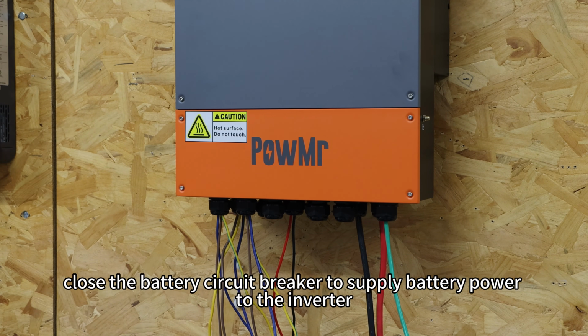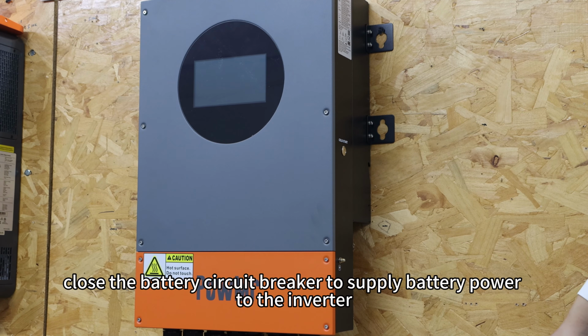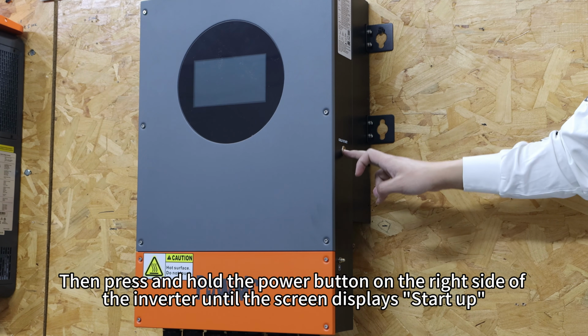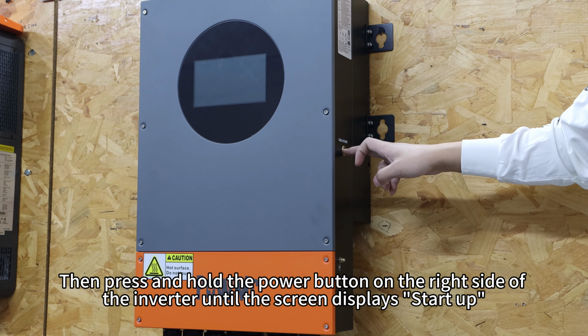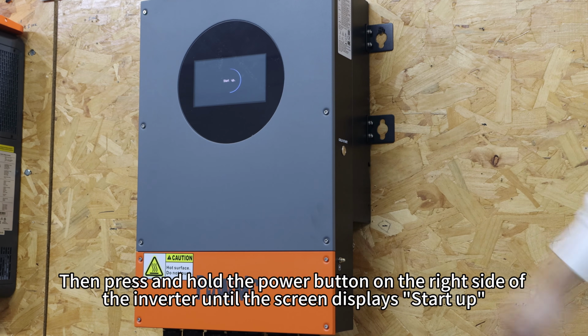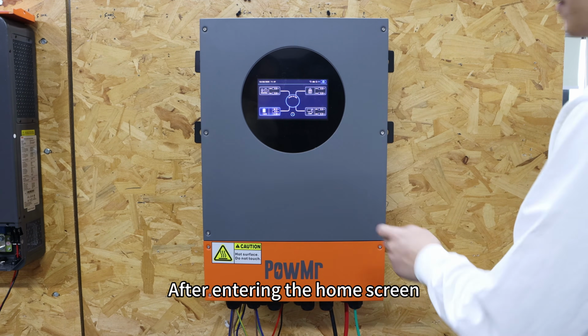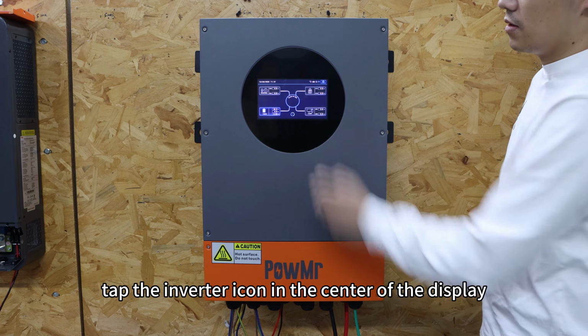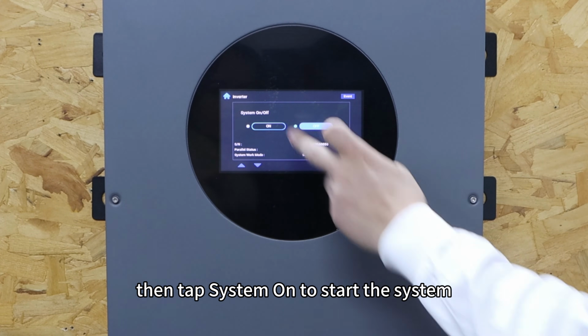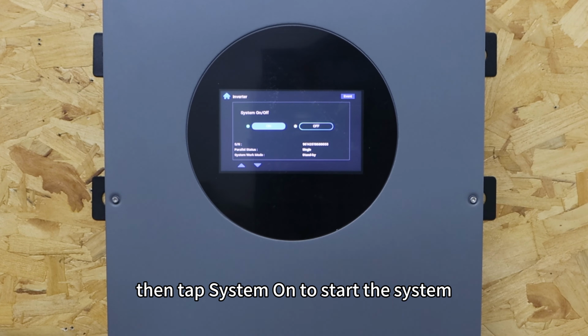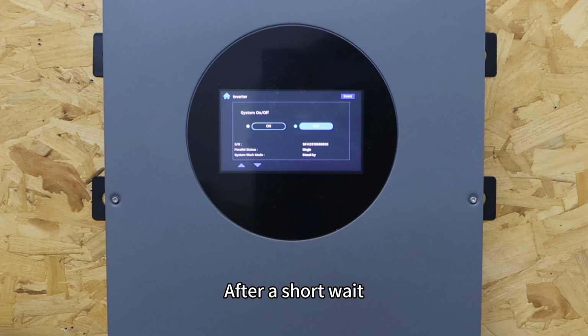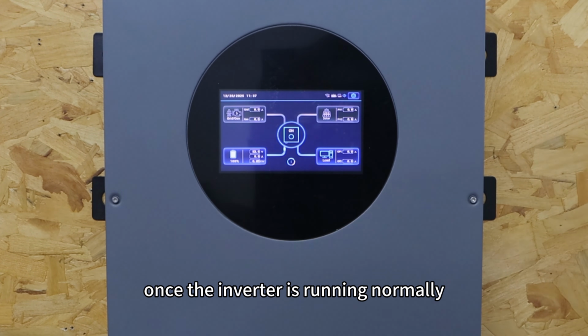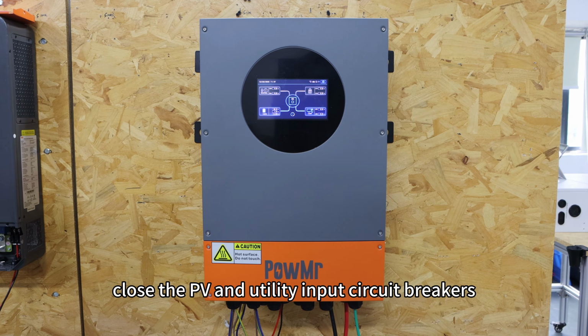First, close the battery circuit breaker to supply the battery power to the inverter. Then press and hold the power button on the right side of the inverter until the screen displays startup. After entering the home screen, tap the inverter icon in the center of the display. Then tap System On to start the system. After a short wait, once the inverter is running normally, close the PV and utility input circuit breakers.